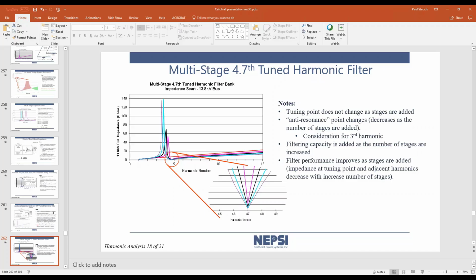But you can see that beneath the 5th harmonic, depending upon the number of megavars I have on, my resonant point has moved down towards the 3rd. The more megabars I put on, the closer to the 3rd I get. But in this situation, the common harmonics are 5th, 7th, 11th on 3-phase networks. And as such, you want to make sure there are no resonances at or above the 5th harmonic, because the harmonics typically start at the 5th and work themselves up from there. You got 5th, 7th, 11th, 13th.